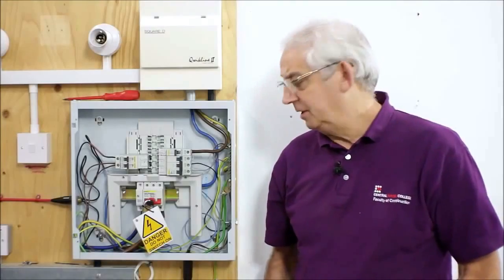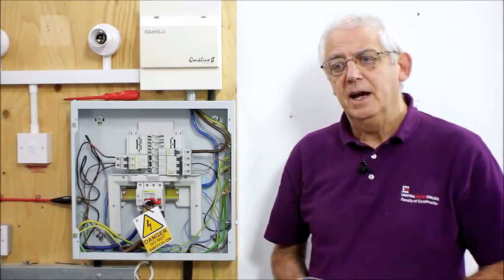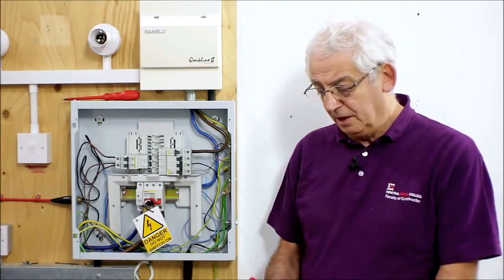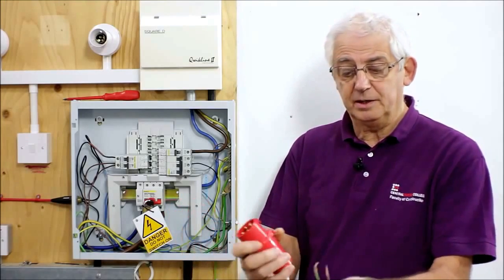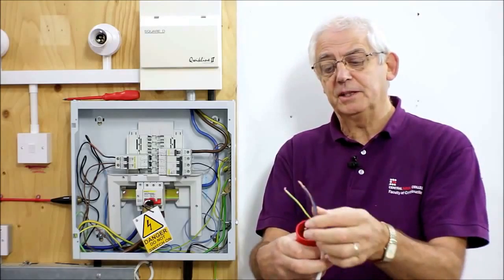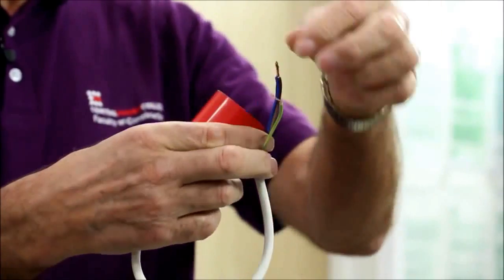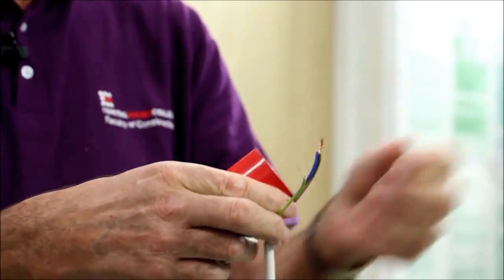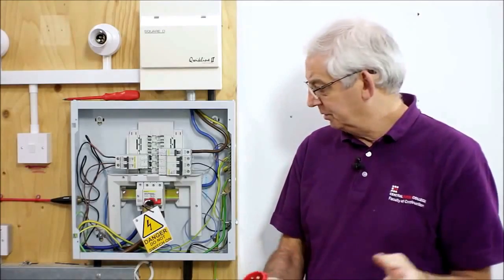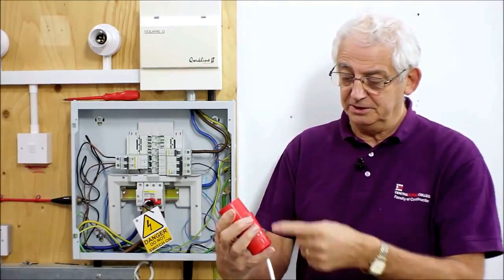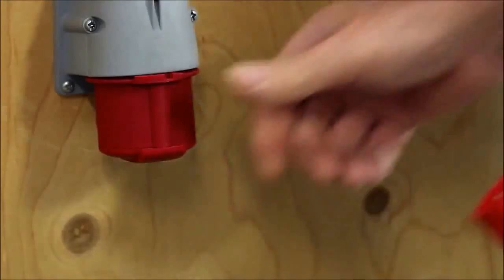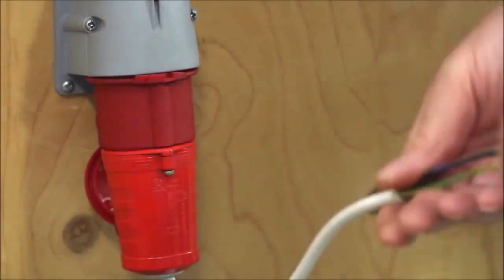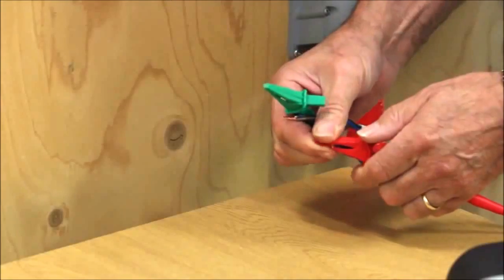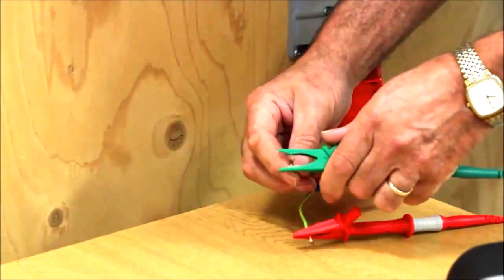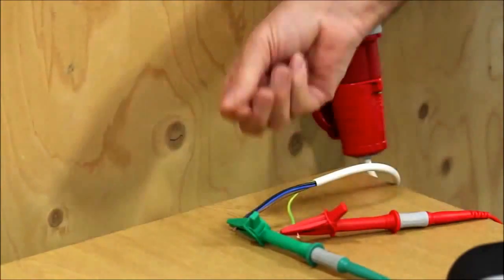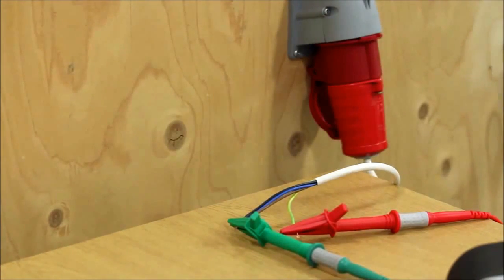So what I've got is I'm going to test to a three-phase plug and we've got a starter in the circuit. What I've done is I've wired up a three-phase plug and obviously it's got three phases, but I've joined them together so that I only need to join the crocodile leads once rather than mess around trying to swap between different wires. It works perfectly well because the only bit of resistance I've got is this piece of cable. So if I plug this into the socket first and then connect my crocodile clips, I need to make sure they're pressed together nice and tight so that I don't get a high resistance joint.